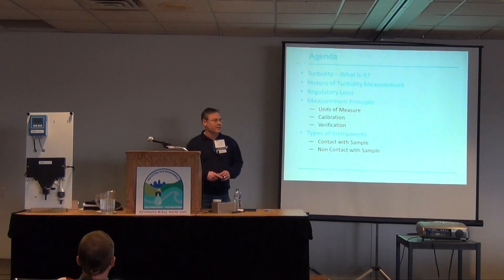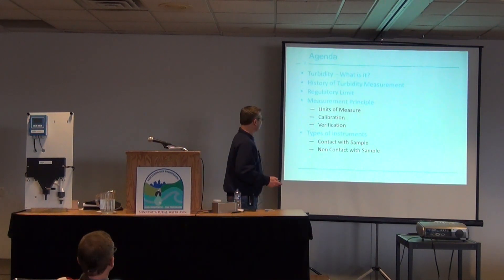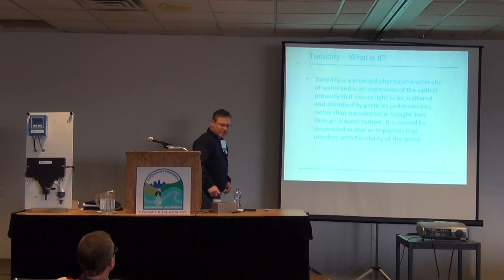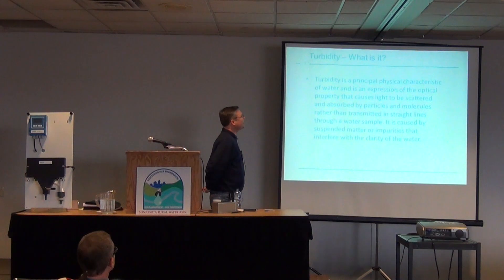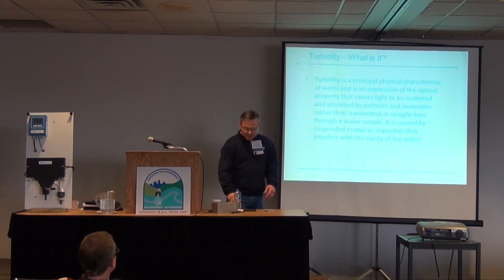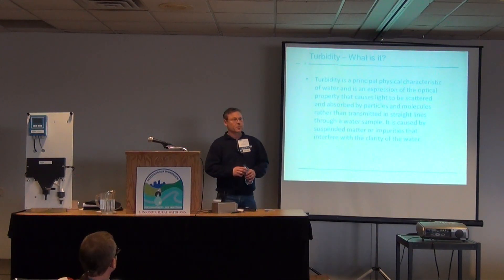Turbidity is a characteristic not just of water — it can also apply to beer. It's an optical property. You use some kind of light source and some kind of photodetector to measure the light absorbed by particles. Something like milk would be very turbid. I've had instruments installed in water plants on Lake Michigan — microfiltration plants — where they're literally measuring turbidity down at 0.006 NTU. Amazingly clean water.